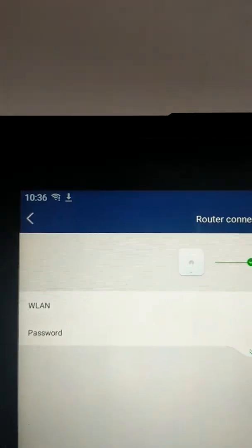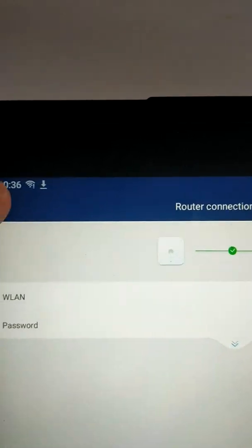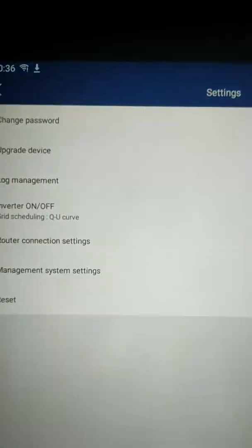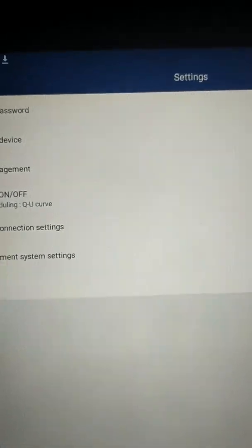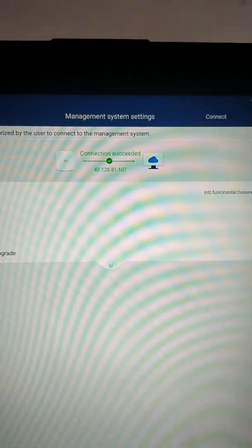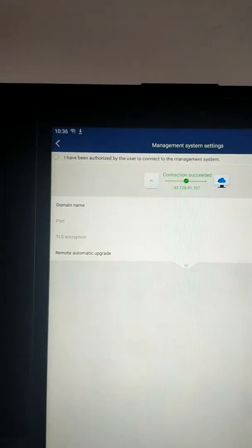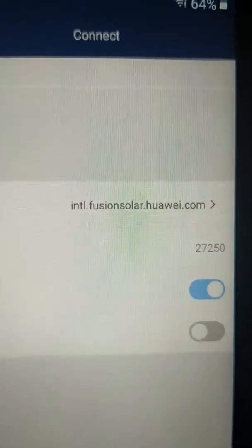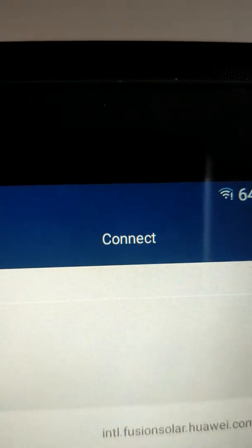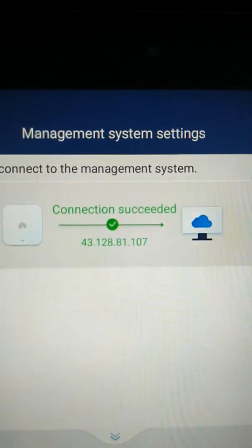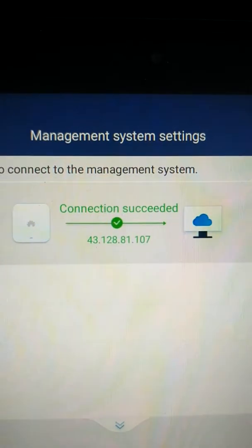Step two, go back. Management System Settings. So, this is where the router is now connecting to Huawei's server on the internet. And what you do is you put a little checkmark in, I have been authorized. You then make sure that that says intl.fusionsolar.huawei.com and port number 27250. And then you click on Connect. And again, 30 seconds later, hopefully, you end up with something looking very much like that.